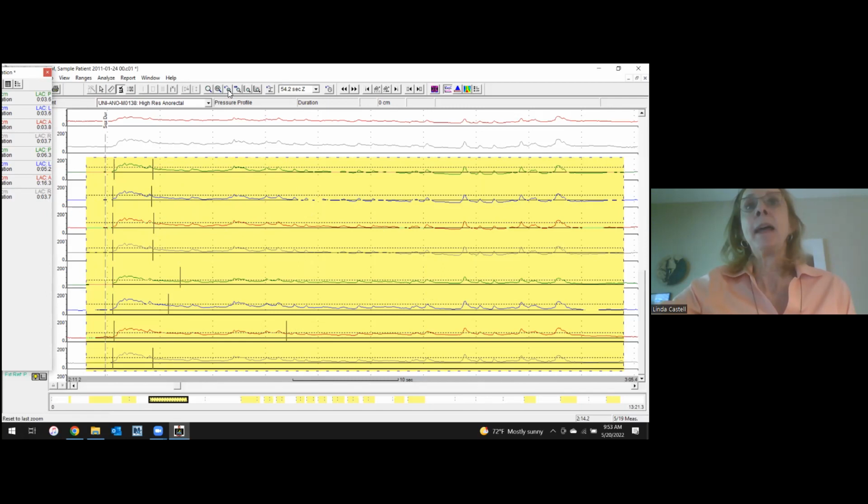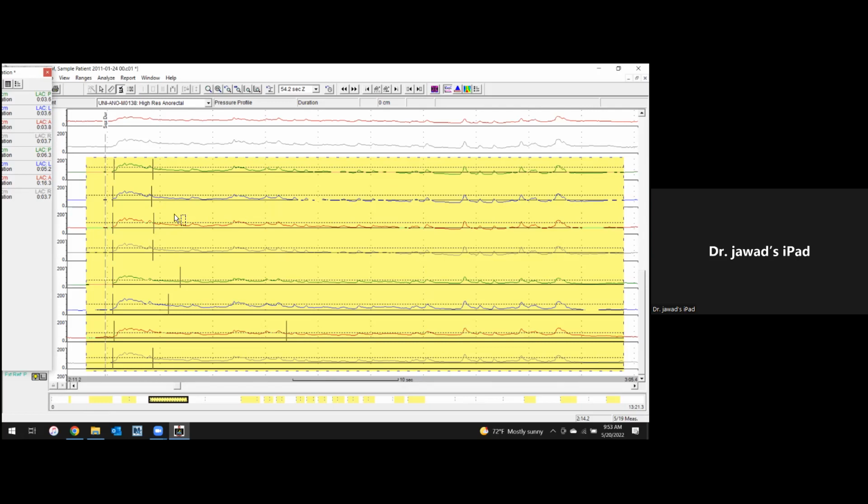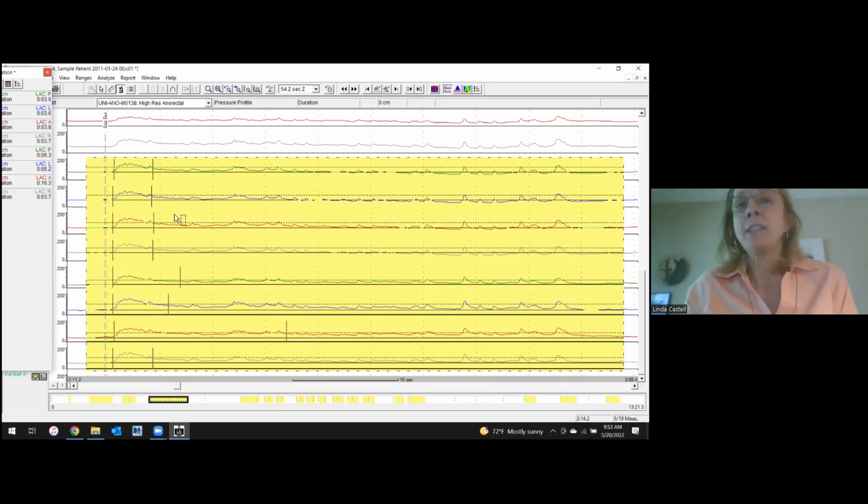So I'm going to demagnify, go to last view, which is the third magnify. Excuse me, how can the computer locate the direction of the anal canal, with the anterior, posterior, left, right, because the anal catheter has no indicator for the direction? Yeah, so on your catheter, each level has 4 sensors built into it. And you can't see them, but they're left, posterior, right, and anterior.